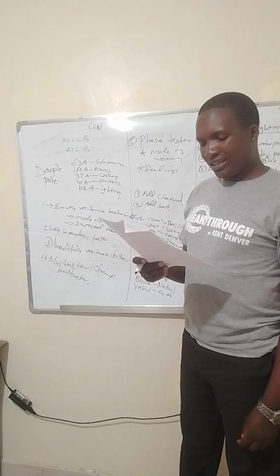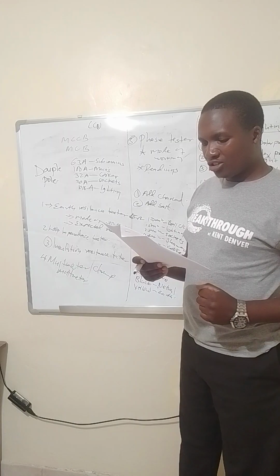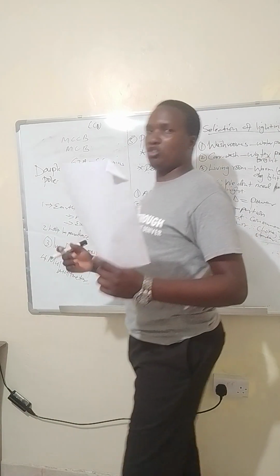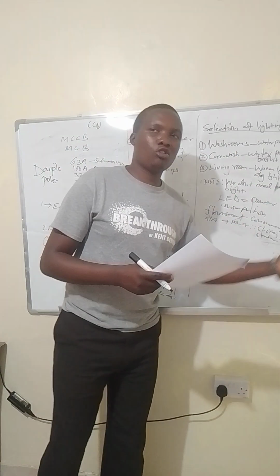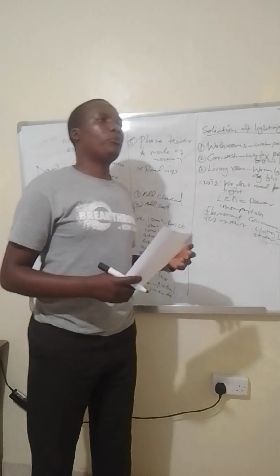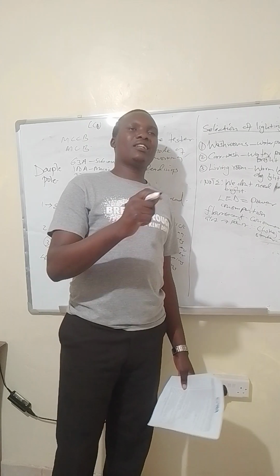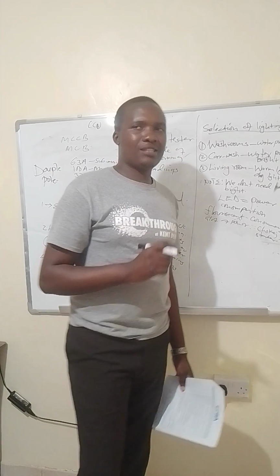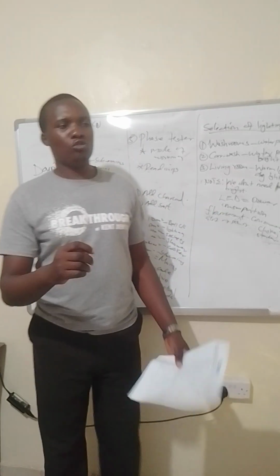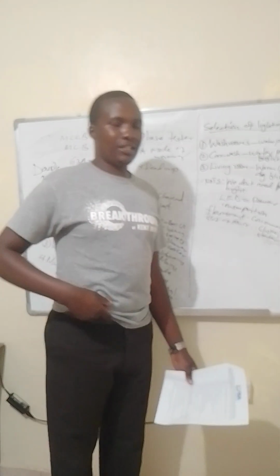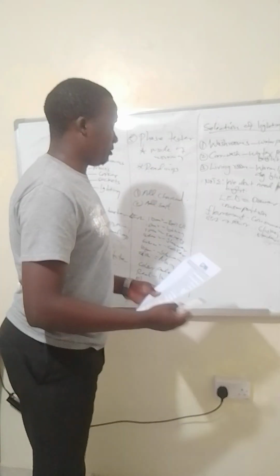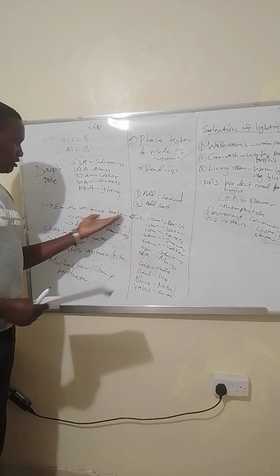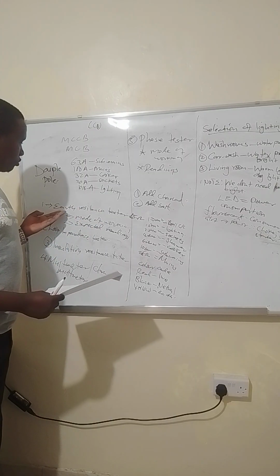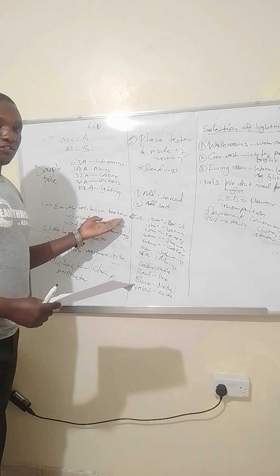Another thing, you will be tested on testing and commissioning of domestic electrical installation. You will be asked how to commission, before you test or commission, or give your project to the owner. What are the things a competent technician needs to do? Number one, you need to do tests before giving your client his project. You need to do an earth resistance test to check if earthing is good.